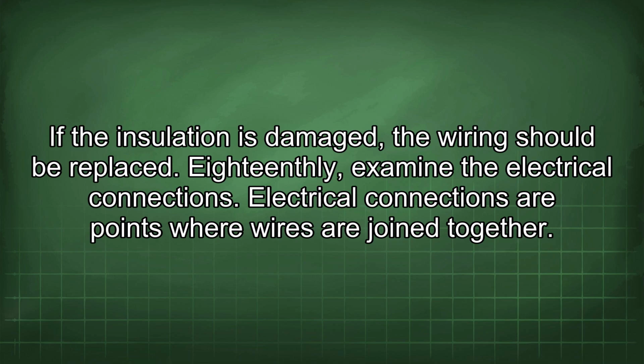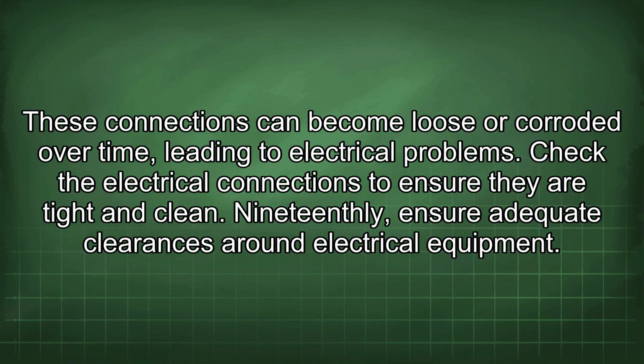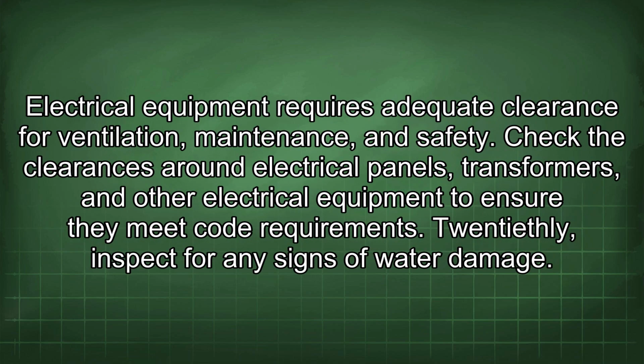18thly, examine the electrical connections. Electrical connections are points where wires are joined together. These connections can become loose or corroded over time, leading to electrical problems. Check the electrical connections to ensure they are tight and clean. 19thly, ensure adequate clearances around electrical equipment. Electrical equipment requires adequate clearance for ventilation, maintenance, and safety. Check the clearances around electrical panels, transformers, and other electrical equipment to ensure they meet code requirements.